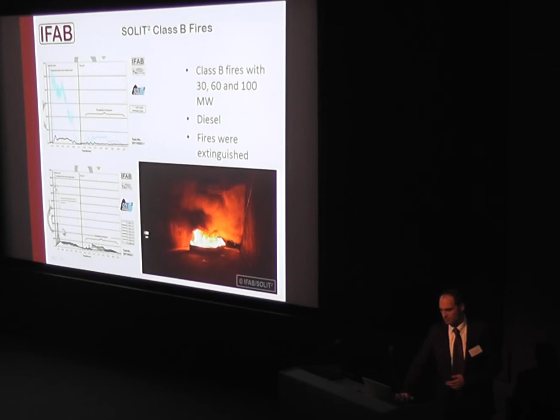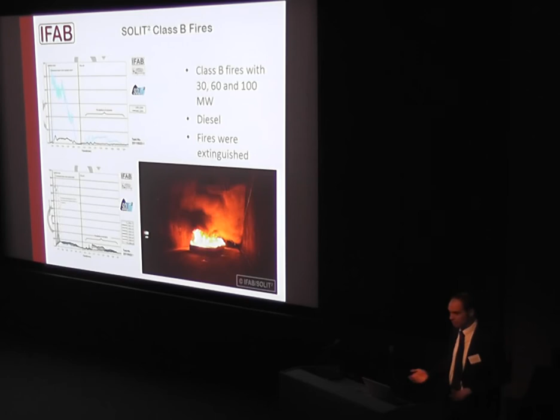And here you see also some temperatures measured a bit downstream, and you see this immediate reaction to the water mist. You have an immediate cooling effect. So even though you have a fire burning there, because the fire is not out yet, the fire is still burning with a significant 50 megawatt, 40 megawatt, you can approach the fire, because the temperatures around the fire are cold enough to go there.